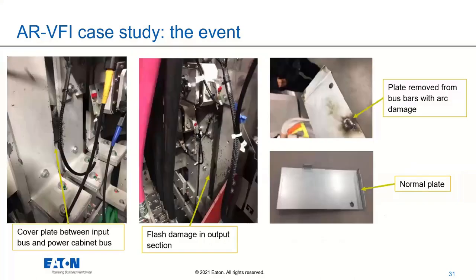So just showing some of the actual fault pictures here, we're looking inside of the low voltage gear. And it's a little bit hard to see, but right behind these two pieces of bus, this is the A and B bus here, there's actually a piece of shipping support, this plate that you're seeing on the right-hand side, that had fallen and slid down behind that. Normally it's taken out of the roof of this gear, and it slid down behind there. And of course, nobody noticed it in this case. But again, they're going through commissioning. And of course, upon startup, you're going to get that arcing fault that would short across here. And remember, this is a 6,000 amp piece of bus work.